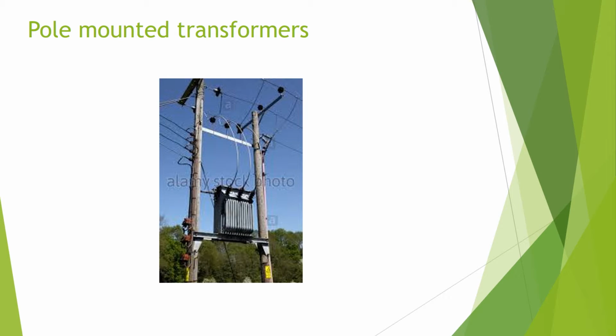Pole mounted transformers. Transformers in rural areas tend to feed individual or small groups of customers, so are much smaller than those that feed urban LV networks. Rural overhead line transformers are designed to be mounted to the pole at high level to prevent danger to the general public from exposed HV and LV conductors. They generally vary in rating from 5 kVA to 100 kVA, and both 3-phase and single-phase units are commonly used.